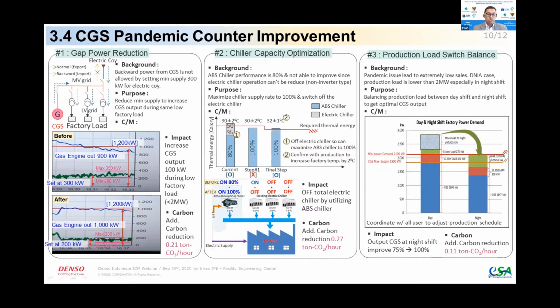For example, before, the factory load condition was 1.2 megawatts, then gas engine output was just 900 kilowatts, because the minimum setting for the electricity company is 300 kilowatts. With some technical solution, with the same factory load, we can manage a higher output for the gas engine, 1000 kilowatts, because we lowered our setting by 100 kilowatts, from 300 to 200. By this, we can have additional carbon reduction of 0.21.